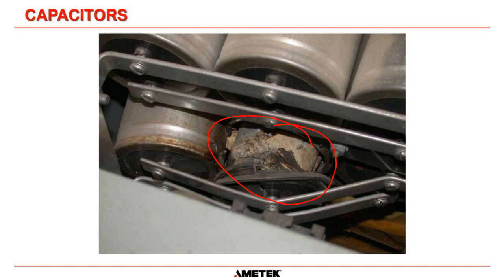And what happened is the electrolyte inside the capacitor dried out. It started heating up. Pressure started building within that capacitor. And eventually, it ruptured quite spectacularly. And not only has it caused that force, and remember, this could have pushed this bus bar onto some other live conductors in the UPS. Not only that, but a lot of smoke would have been released when this capacitor blew. You can see that there is some residue here from this capacitor exploding.